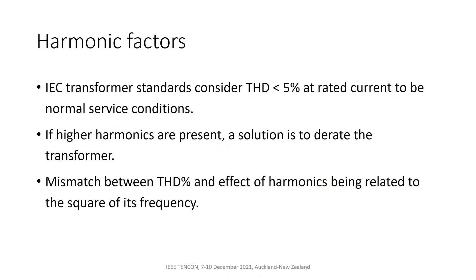So what we looked at doing here, we took a section of the network in Australia, and then we started to have a look at what is actually happening in terms of the harmonics. So here we've got two, I suppose, medium-sized PV arrays. Obviously, this is not a very large solar farm. I mean, this is around about 1 megawatt size. So in some ways it's pretty substantial, but it's not the biggest that can be out there. And we have these two PV arrays, and they're connected through these inverters, and then we have our transformer, and then it's stepped up to the MV network, which is owned by the distributor.